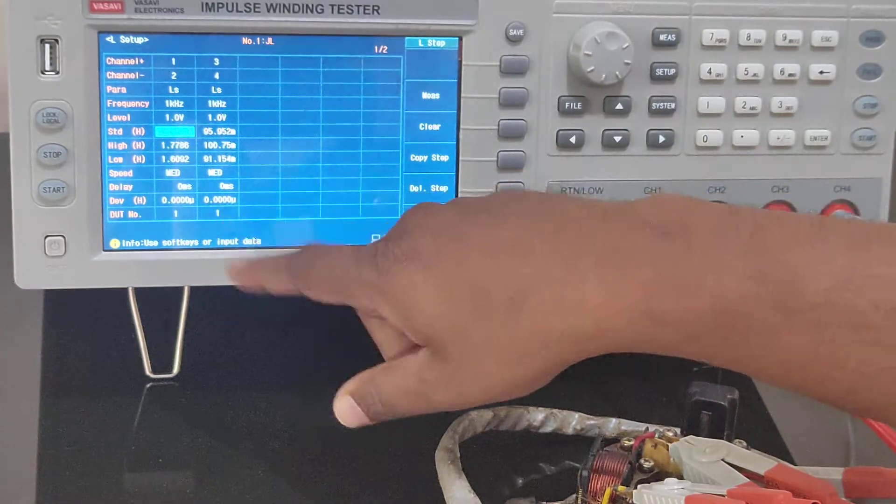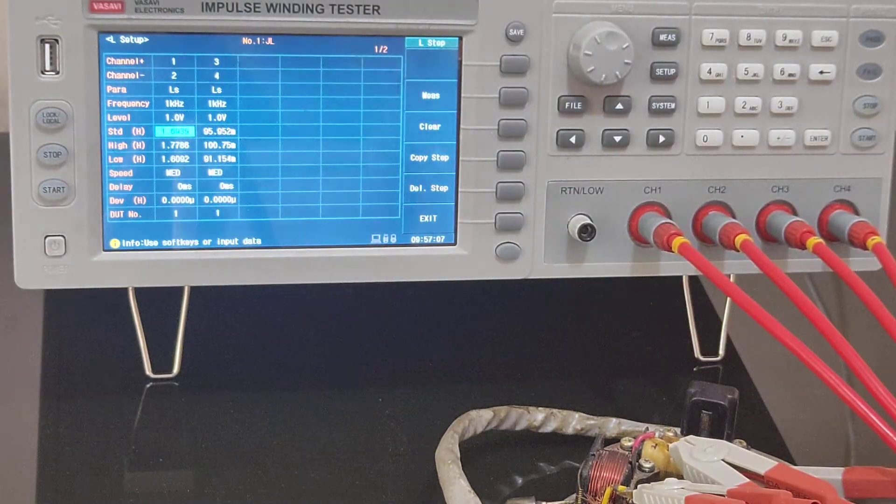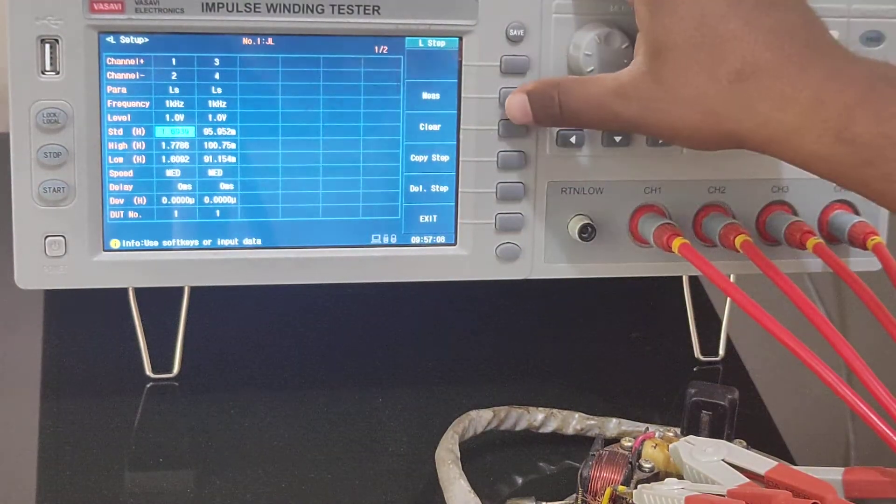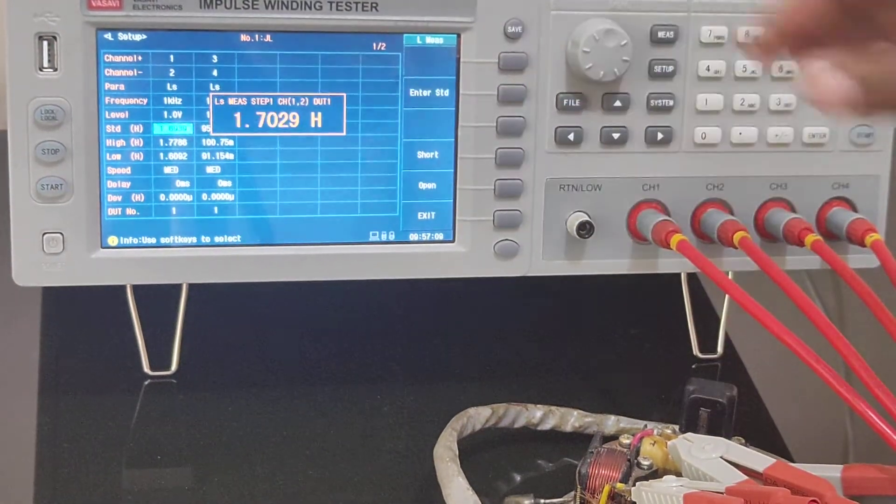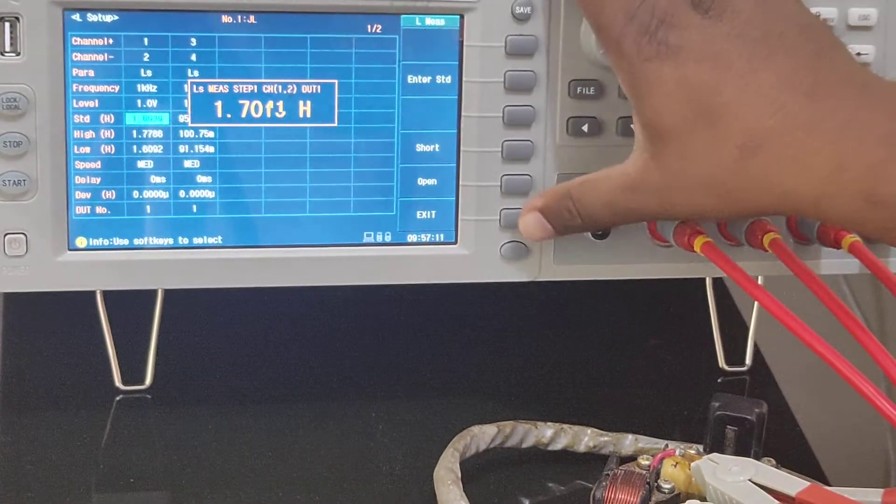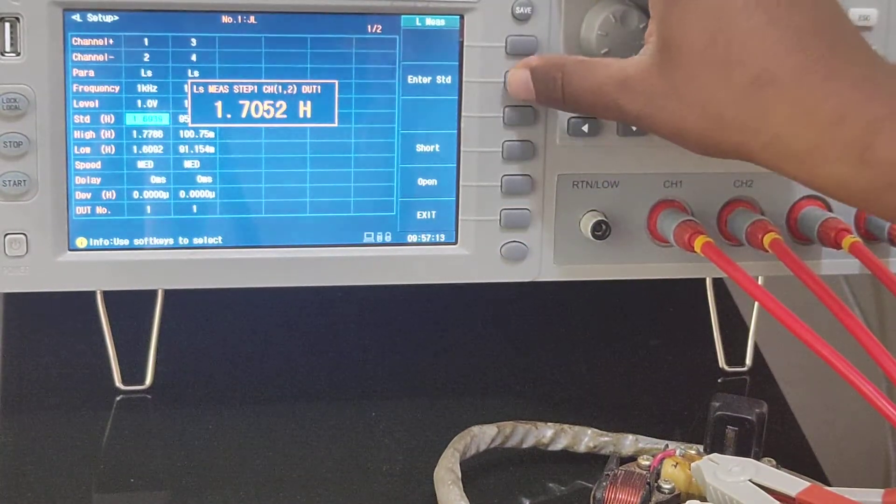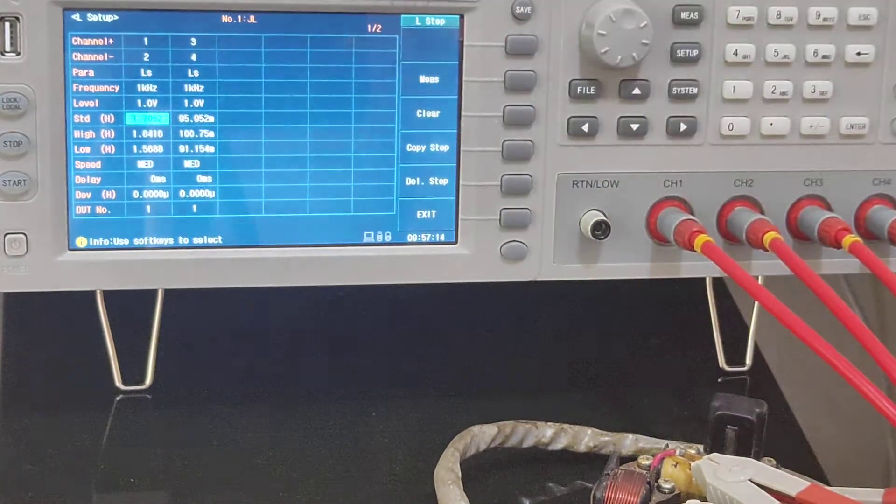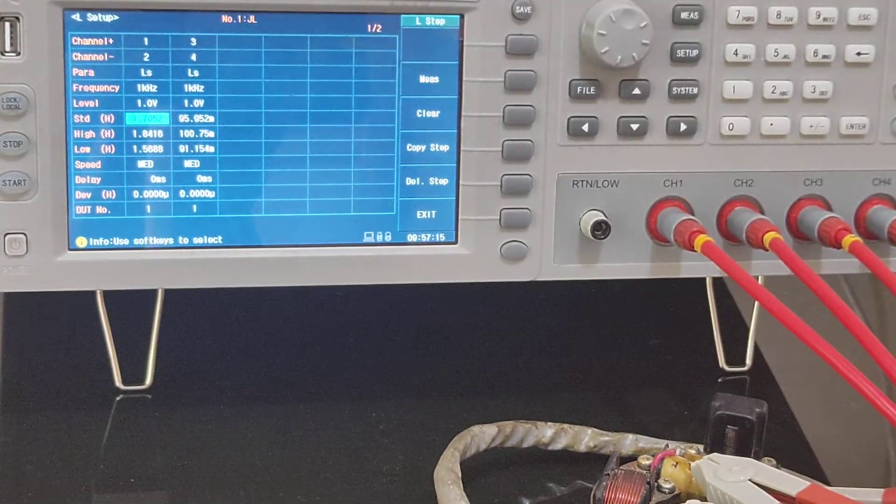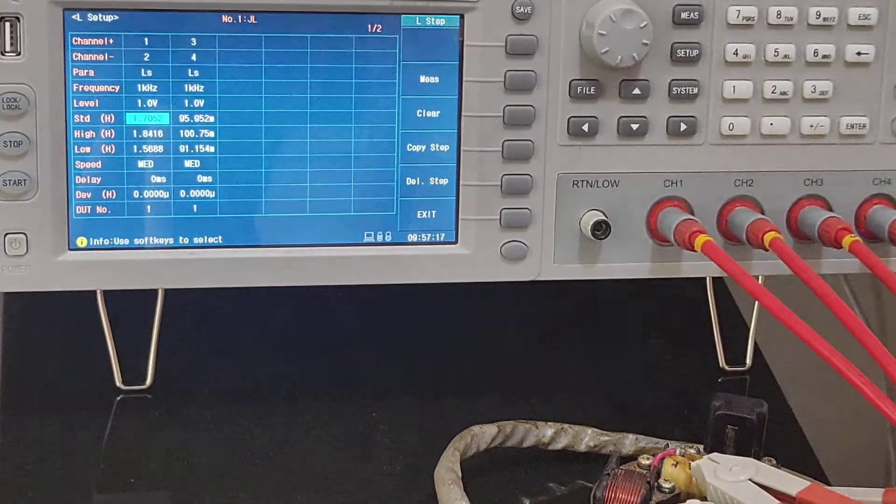It's the same way like what I showed you in DC resistance. In case if you know the standard value you can enter it, or you can simply press measure. It will give you the measured value. If you feel that is okay, press the button for selecting it and these are the limits and this is the speed.